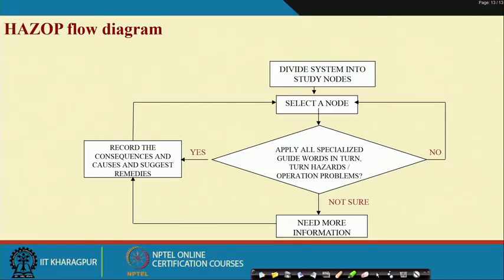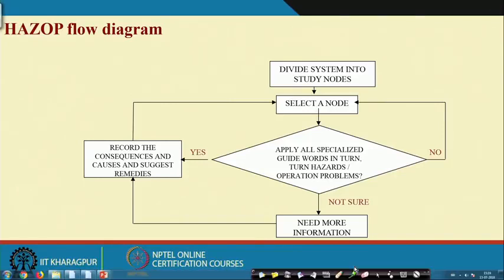Repeating the procedure in terms of a diagram: divide the system into study nodes, select a node, apply all specialized guide words in turn to find hazards or operational problems. If it is not a hazard, go to the next; if you are not sure, collect more information; if yes, record the consequence and causes and suggest remedial actions. This way a hazard list will be prepared.